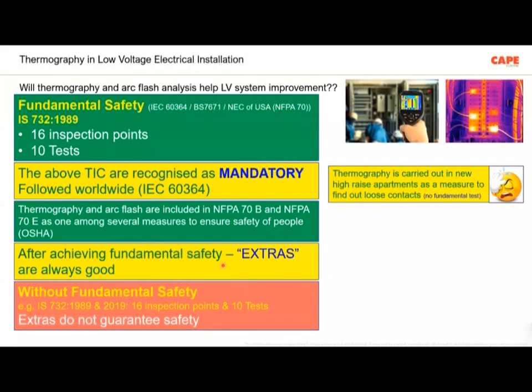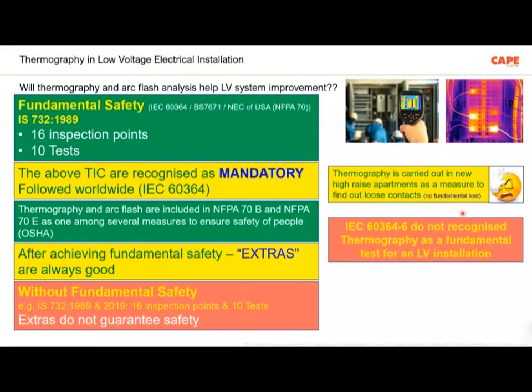And recently in one of the buildings, a new high-rise apartment in Bombay, I even saw them doing thermography to find out loose contacts in the wiring. So they are not doing any of the fundamental safety measures. I would say 90% of the fundamental safety measures are missing, but finally a thermography for the wires which are enclosed inside the conduit is made. This is really not at all acceptable. You are violating the basic requirements.